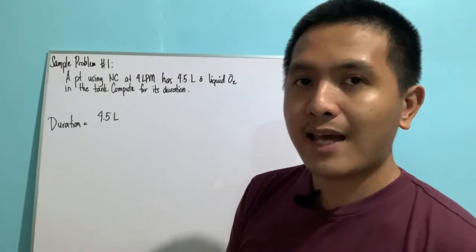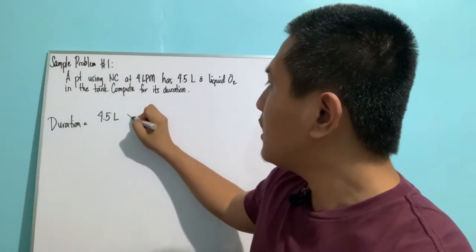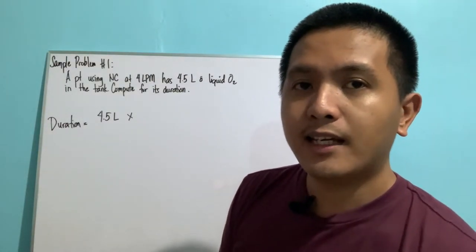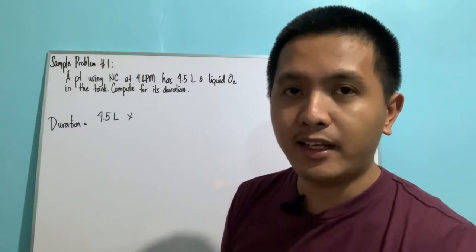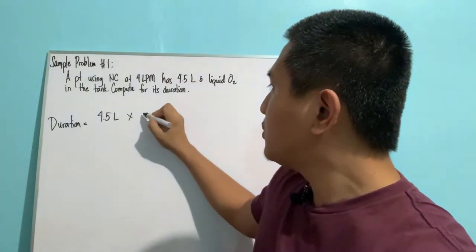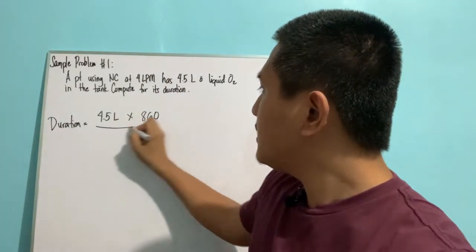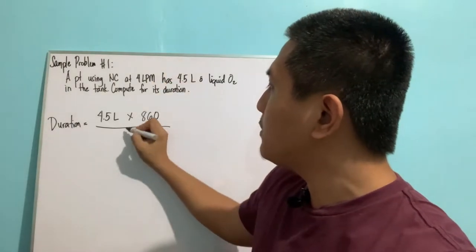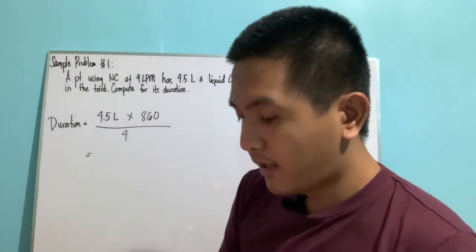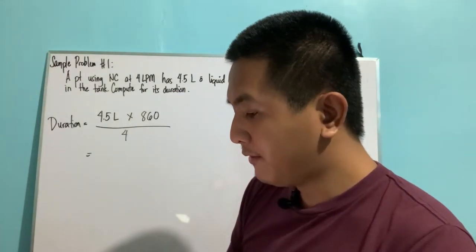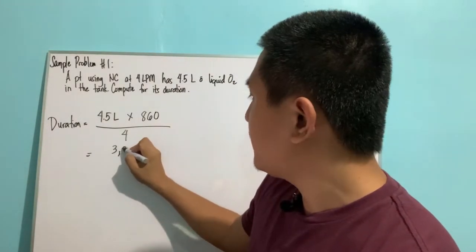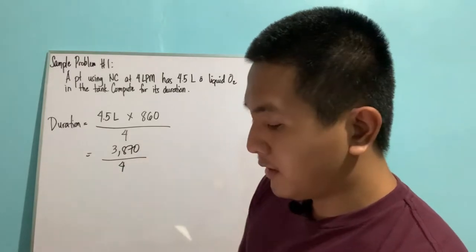We need to convert this liquid oxygen into gaseous oxygen. One liter of liquid oxygen is equal to 860 liters of gaseous oxygen. To convert, we simply multiply 4.5 liters by 860, and then divide by the flow rate, which in this problem is 4 liters per minute.